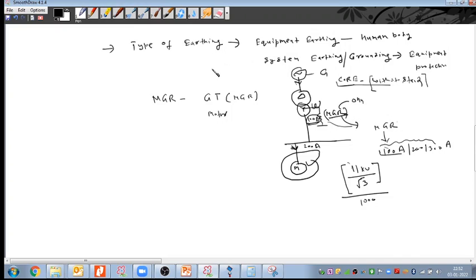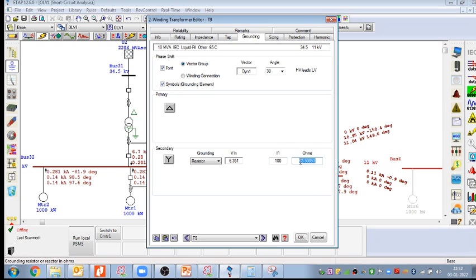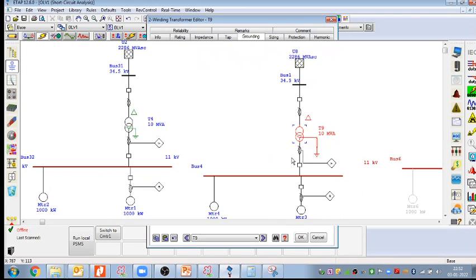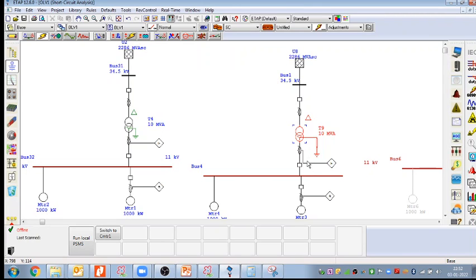Right, sir. Absolutely. If I took 200 ampere and my client asks me why I have taken 200 ampere, I can explain in this manner. Considering 200 ampere is the full load current, the core is designed for 200 ampere. So I limited my full fault current to 200 ampere, and to limit the fault current to 200 ampere, I calculate my NGR rating as this right now. Right, sir.